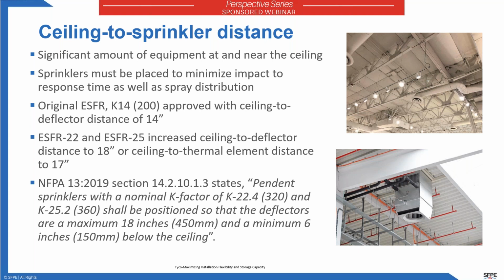The original ESFR sprinklers, the K14s, were approved with a ceiling to deflector distance of 14 inches. When the ESFR 22 and 25 came along, they were able to increase ceiling to deflector distance to 18 inches. Just to make you aware, the FM standards actually measure sprinkler location not to the deflector, but to the center line of the thermal element. So when you read, say, FM 2-0 or 8-9, it talks about sprinkler location, you'll see ceiling to thermal element distance of 17 inches for ESFR 22 and 25, as opposed to 18 from NFPA 13, which talks about ceiling to deflector. So there's a little difference, but essentially, based on sprinkler dimensions, they're pretty close.